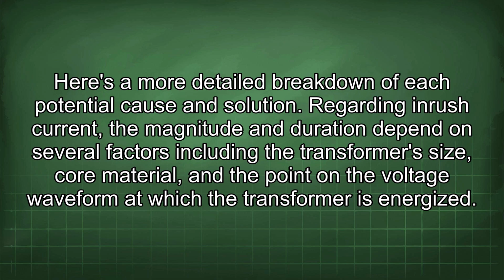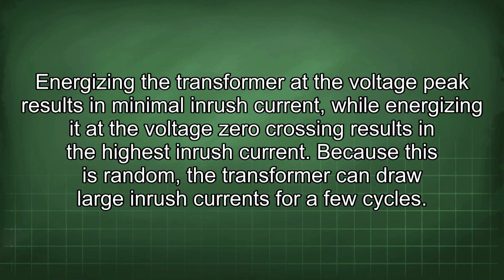Regarding inrush current, the magnitude and duration depend on several factors including the transformer size, core material, and the point in the voltage waveform at which the transformer is energized. Energizing the transformer at the voltage peak results in minimal inrush current, while energizing it at the voltage zero crossing results in the highest inrush current. Because this is random, the transformer can draw large inrush currents for a few cycles.